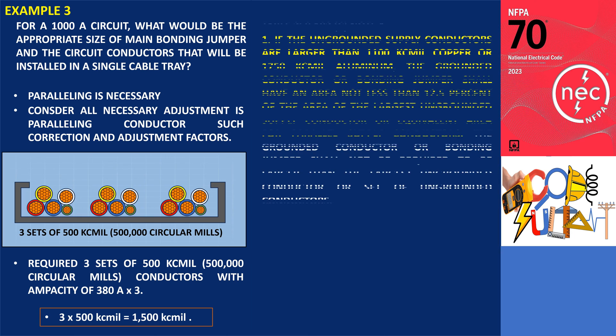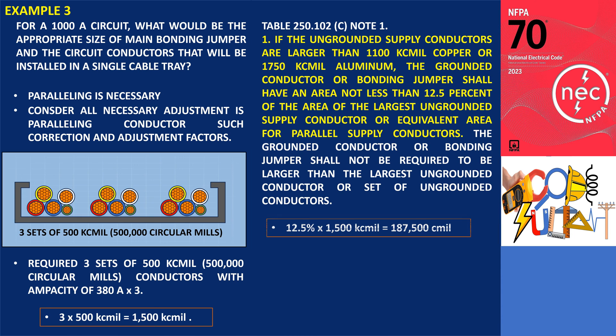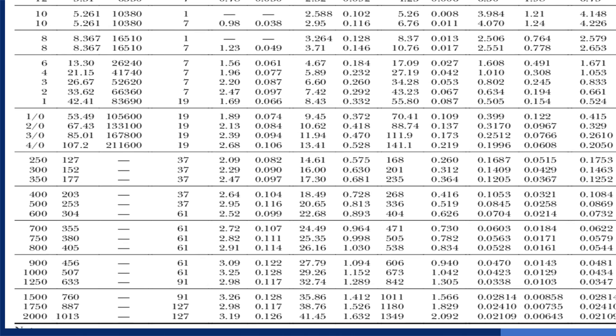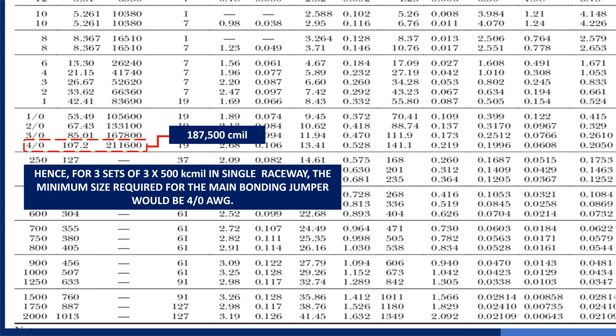Following Note 1, we need to consider 12.5% of the 1,500,000 circular mils, which equals 187,500 circular mils. Referring to Chapter 9, Table 8, we find that the minimum size for the main bonding and system bonding jumper would be 4/0 AWG copper, as the 3/0 AWG below it only accommodates 167,800 circular mils. Hence, for this situation, the minimum size required for the main bonding and system bonding jumper is 4/0 AWG.